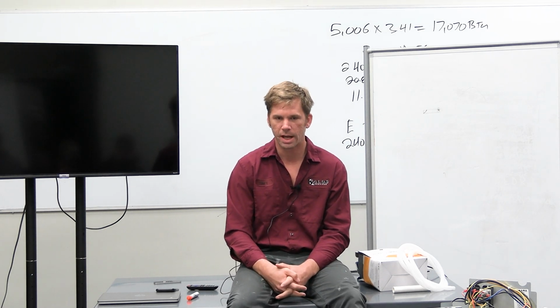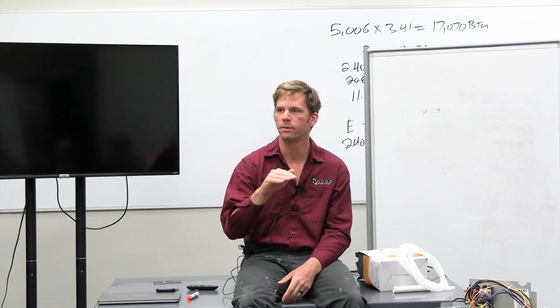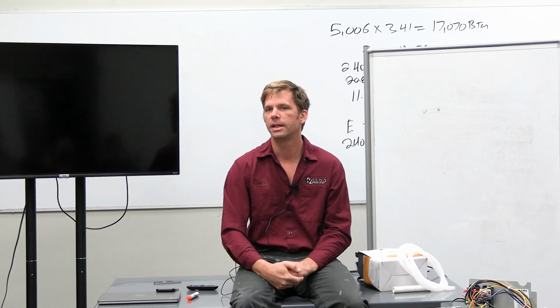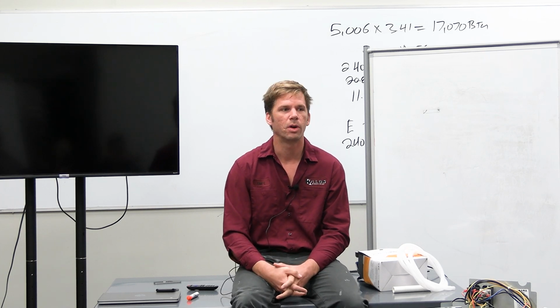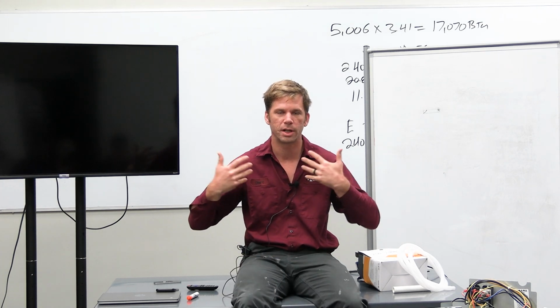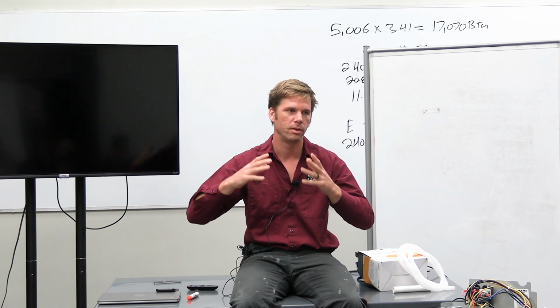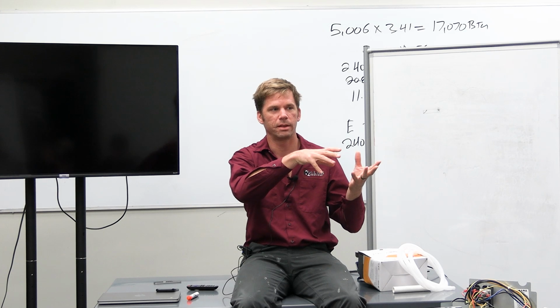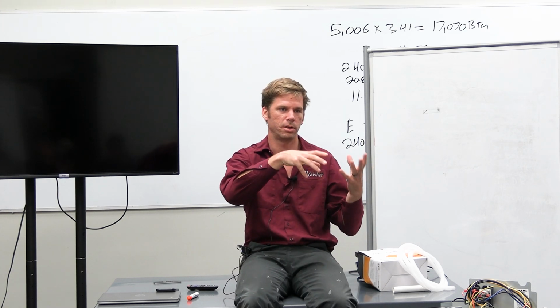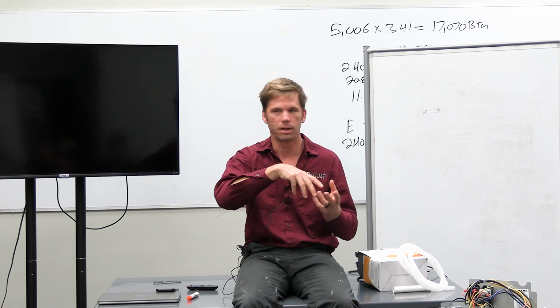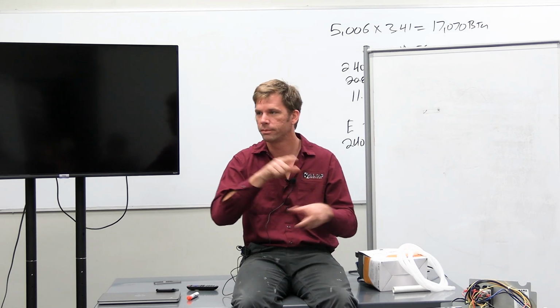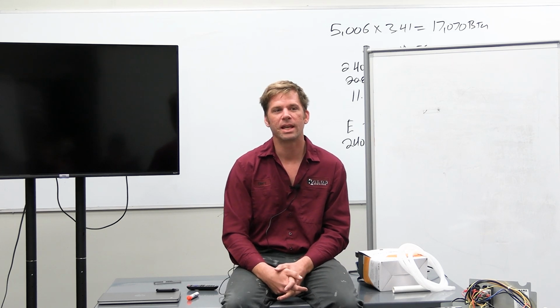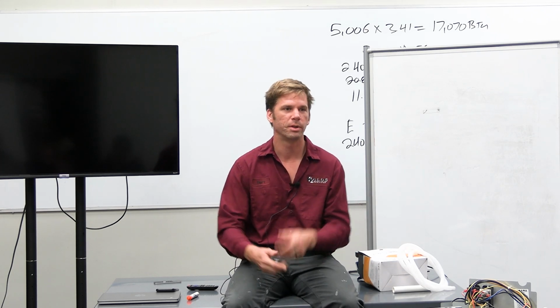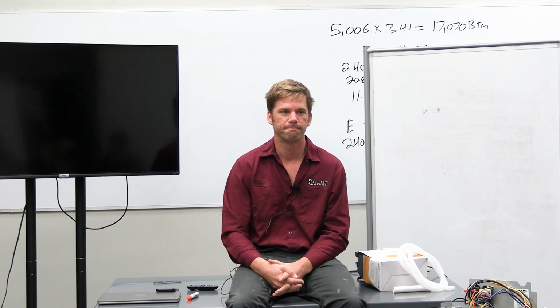So after your heater has actually lit and you've proved flame through the flame sensor, the next safeties that could potentially be a problem would be, let's say, not enough combustion air being drawn in. Your flue pipe, your exhaust pipe coming out the side, could have bugs or critters or junk inside of it, or inside the blower wheel. Yep, some animal, a bird nest. Yeah, there's two birds. So anything related to the airflow could be clogged with critters because you're dealing with something that's sitting outside.